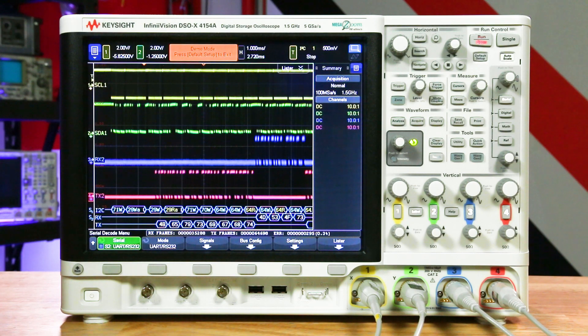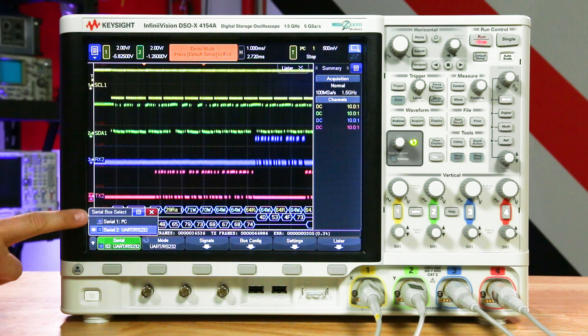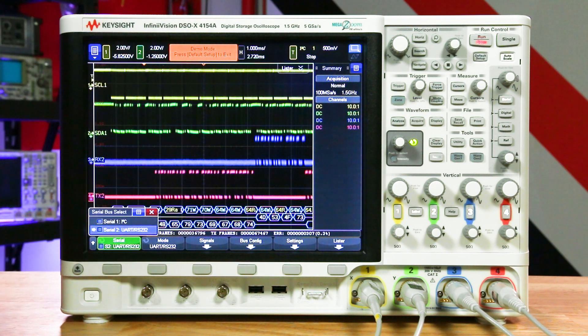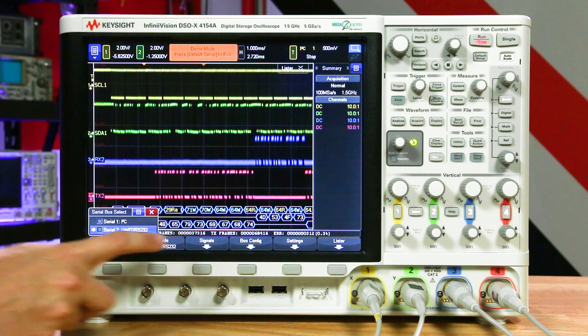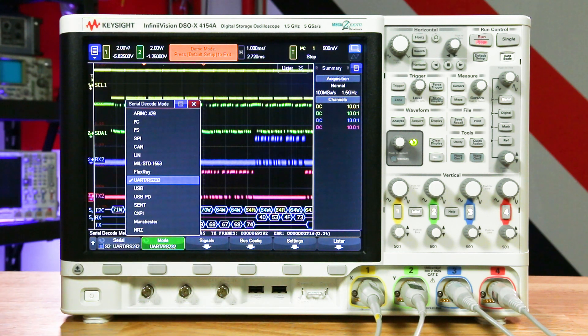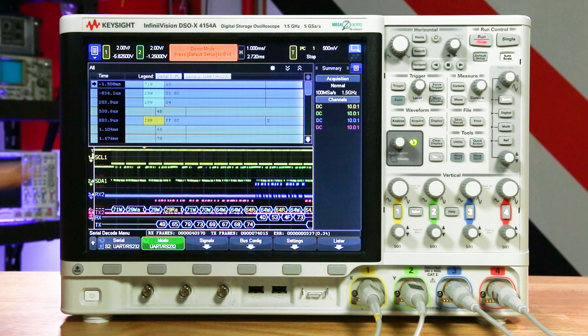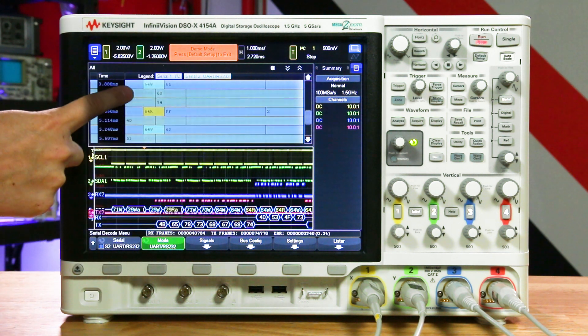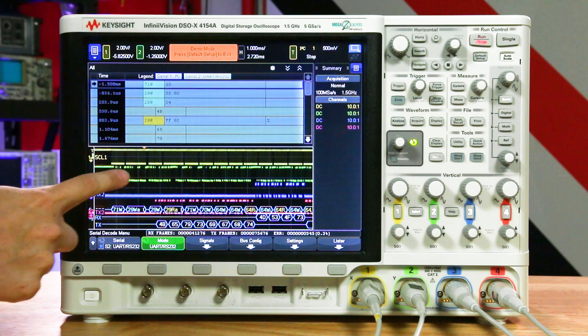And lastly, you can also simultaneously analyze two types of serial buses using the dual bus time interleaved decoding. To initiate this, you simply turn on two serial bus types when you're setting up the serial options. Set up each bus to the specified mode and set your trigger. With this, you can see if a bus is triggering the appropriate events in another bus, or you can view the timing of events between two buses.